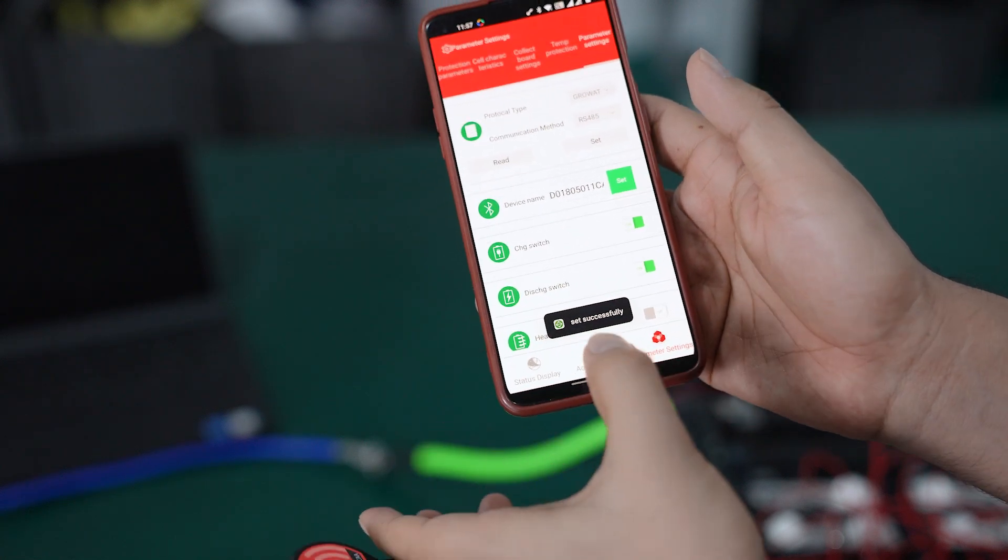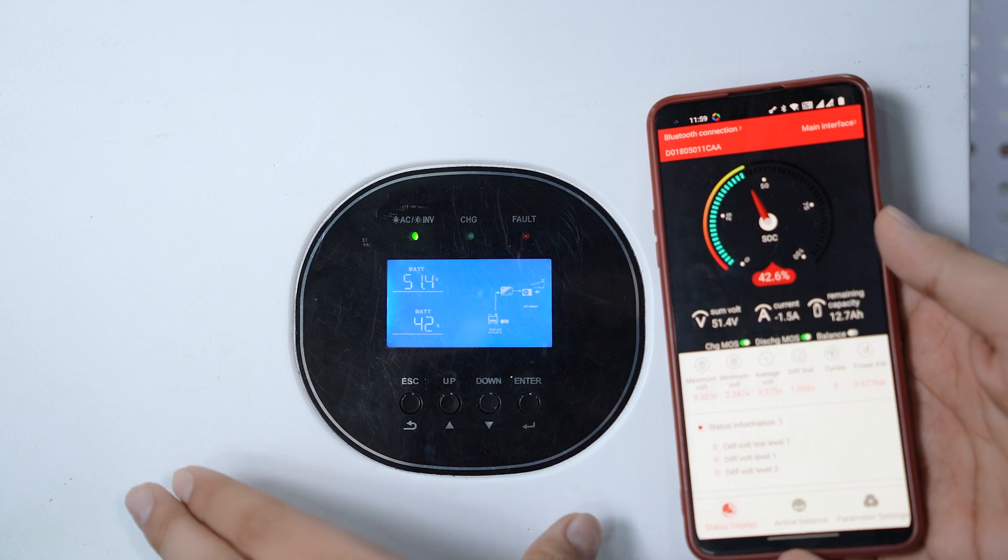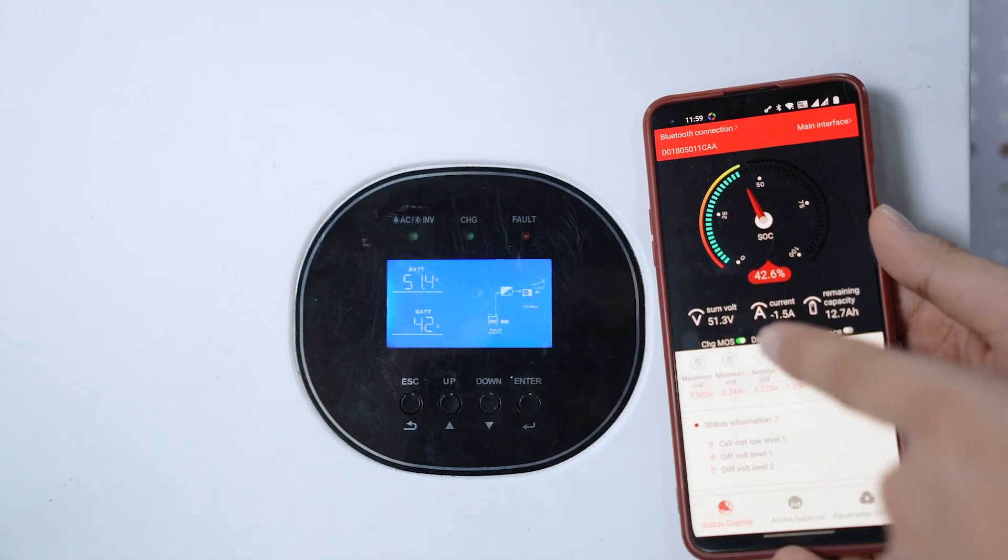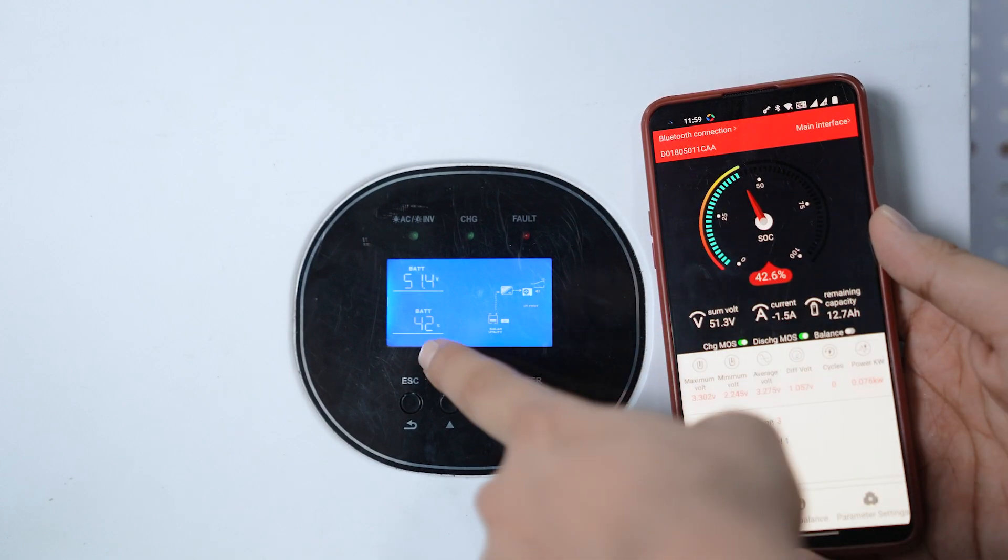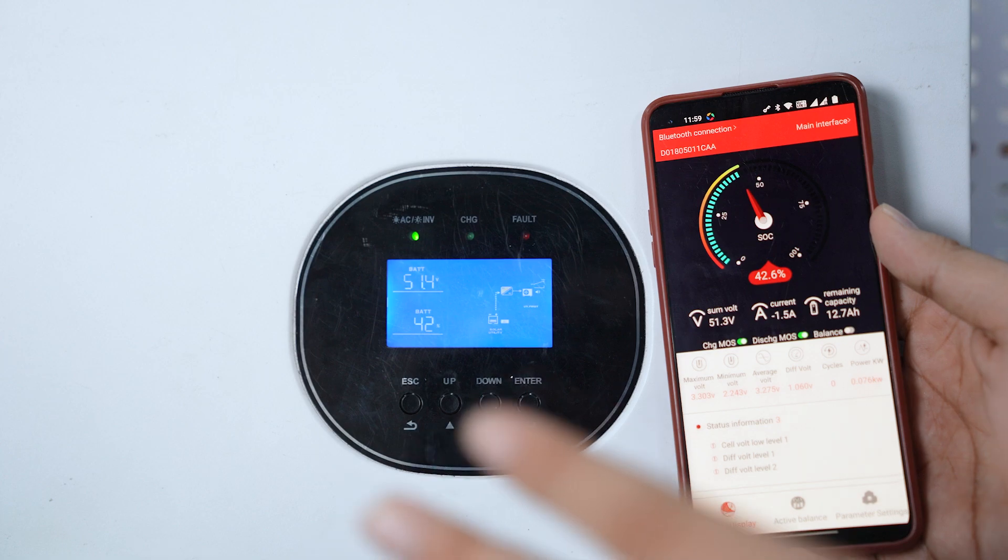You can see here that the voltage shown in the inverter and the app is the same: 51.4 volts. The SOC is 42% here and the same is shown on the inverter, so the BMS and inverter are correctly connected.